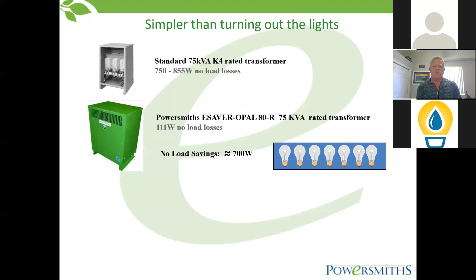Look at a standard 75 kVA transformer, just a standard one you see everywhere in every building. It's a very common transformer. By code, if you have a 225 amp 42 pole panel, you've got to have a 75 kVA transformer. So that transformer is just sitting there doing nothing. You go home at night, it's got 750 to 850 watts of no load loss, just sitting there humming along.